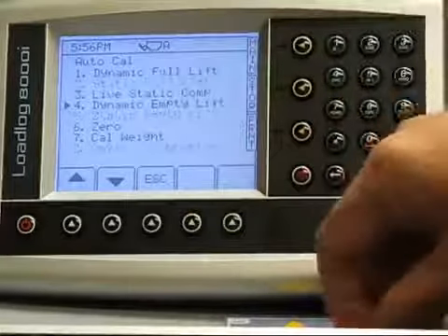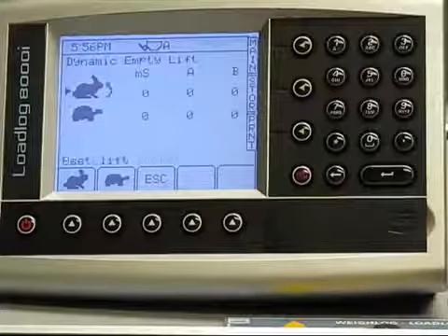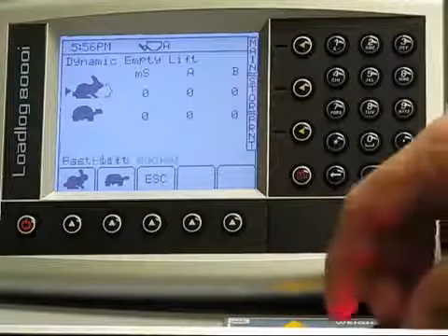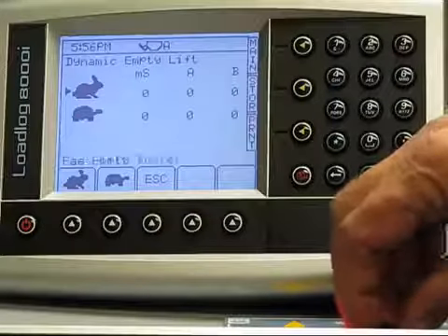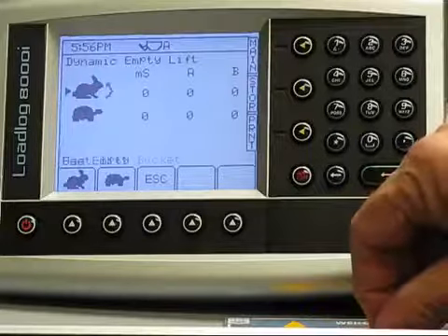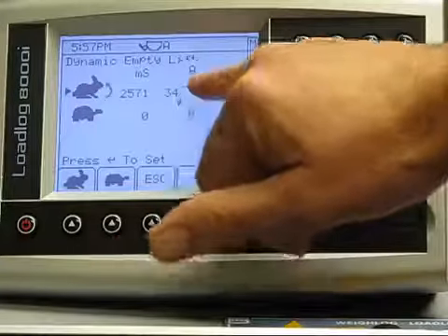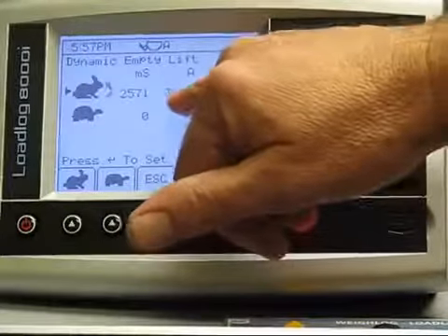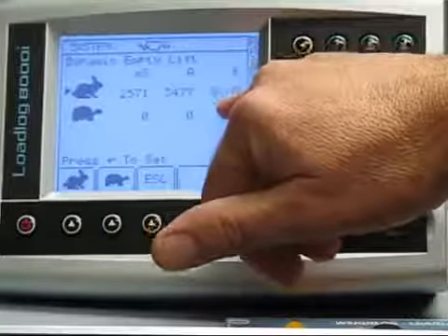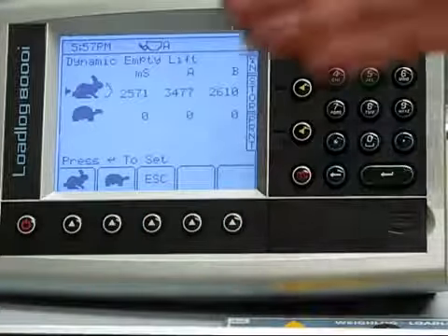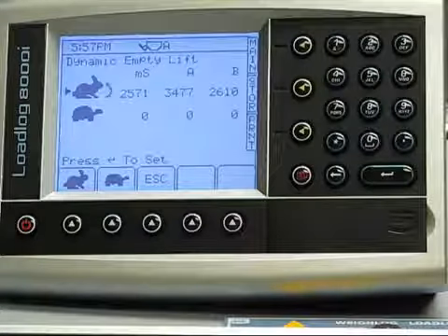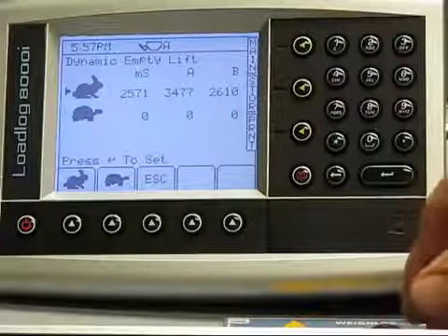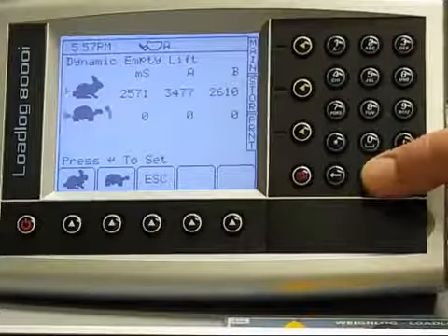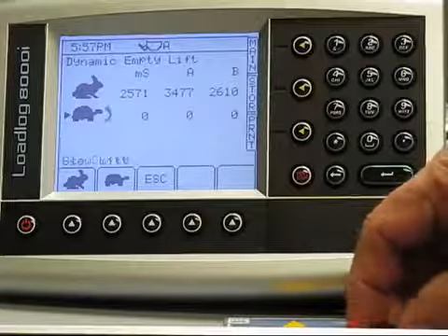We go to the dynamic empty lifts, which is, again, no weight in the bucket. And again, we are going to do both a fast and a slow lift. Please note that the sensor A frequency has gone down substantially because we don't have much weight on it. And third, look over here at sensor B, which is the return sensor, and really not much has changed there. The B sensor will change some, depends a fair amount on the machine. But again, we're satisfied with that result, so we press the enter key.